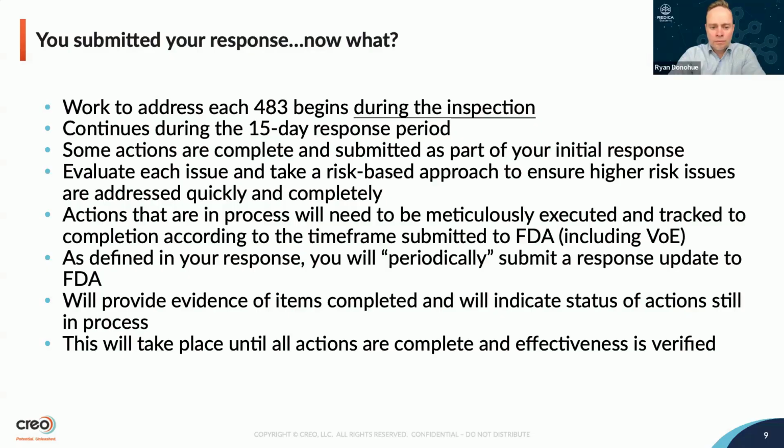And then the ones that maybe are not as critical, say like that internal audit finding, that one might not be as critical as lack of process validation or complaints that have late MDRs, right? So you definitely have to risk rank your response and the timeframes and the containments and the corrections that you're taking as a result of what has happened.